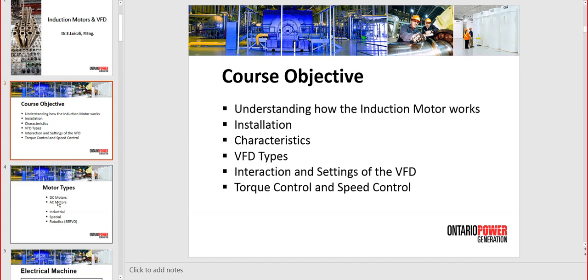What's the difference between soft starter and VFD, and then what is a full regen drive, active front end drive, and so on. So we have different types, and also we have the major two classes, which is motor starter, soft starter, or VFD.